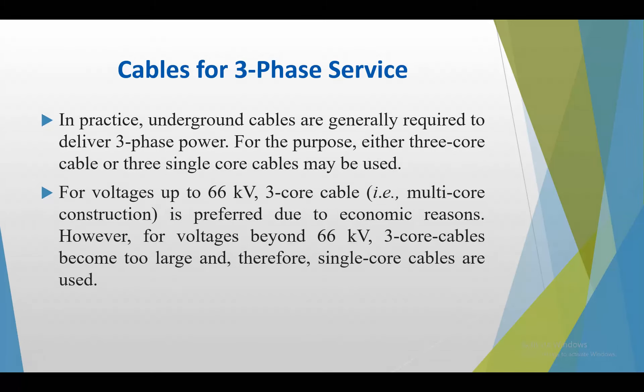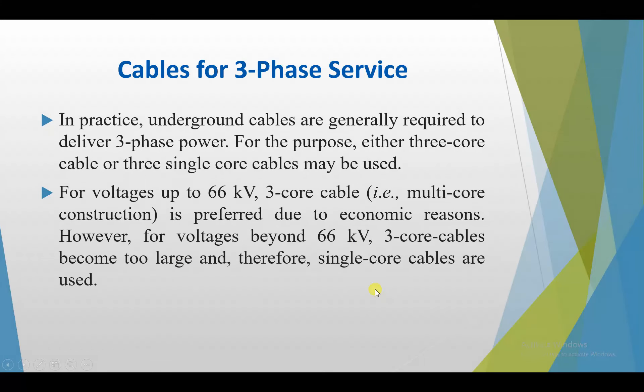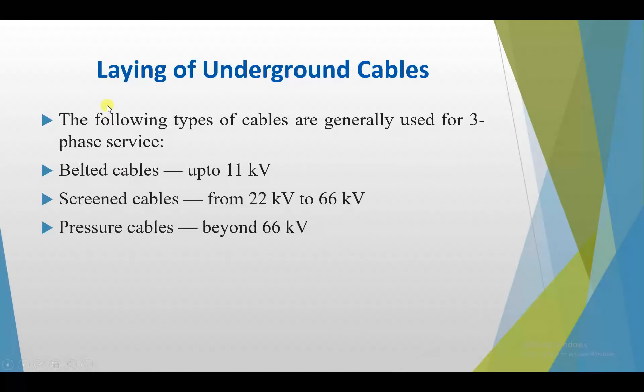For voltage beyond 66 kV, three-core cables become too large and therefore single-core cables are used, since cables are made of many components — conductor, sheath, screen, insulation — making them expensive. The types of cables generally used for three-phase services are: belted cable up to 11 kV, screened cable from 22 kV to 66 kV, and pressure cable beyond 66 kV.